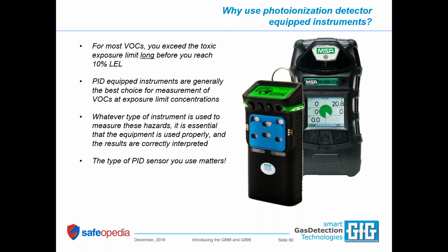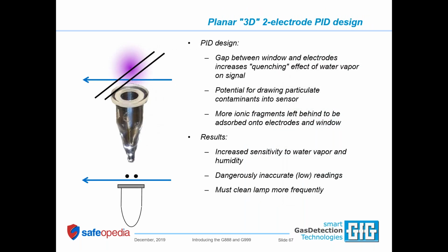Why do we use a PID? PID is the way we measure VOCs. You don't want to measure VOC vapor in the LEL range, even if the sensor is good for it. Even if you were to set the alarm at 5% LEL, you're going to exceed the toxic exposure limit before the alarm goes off. So we want to take action at a much lower concentration. That's why we use the PID.